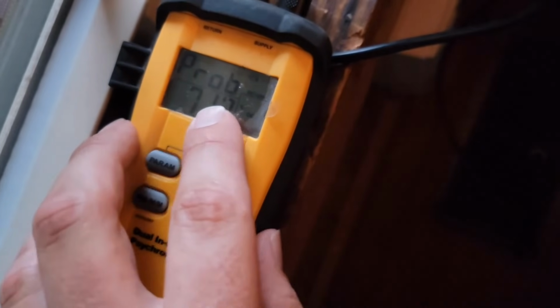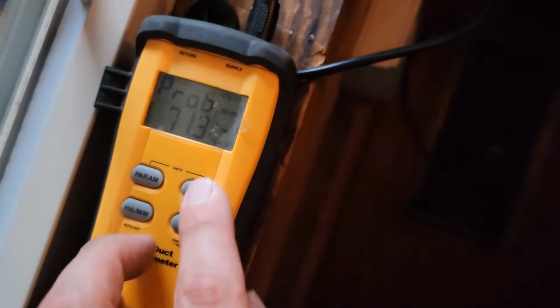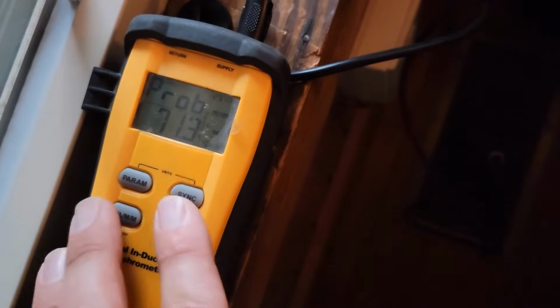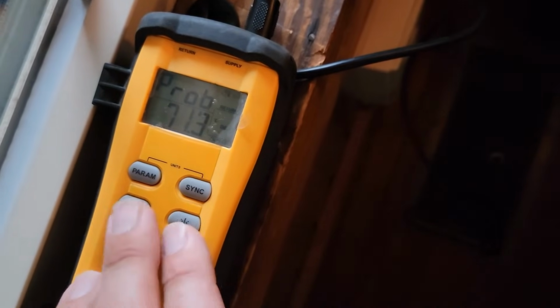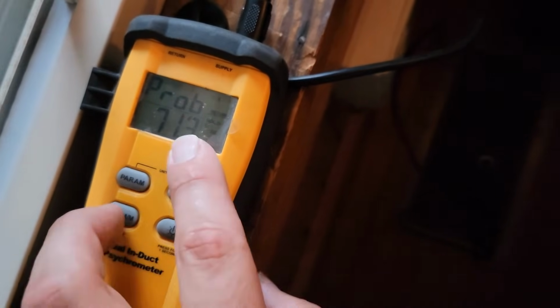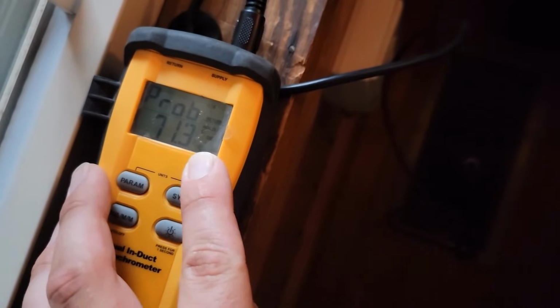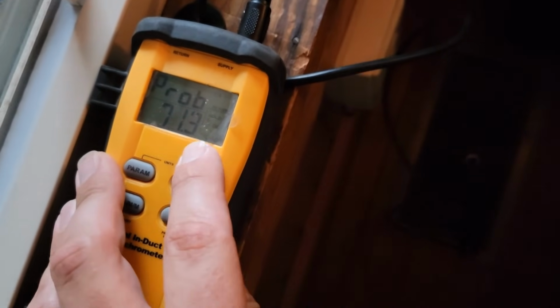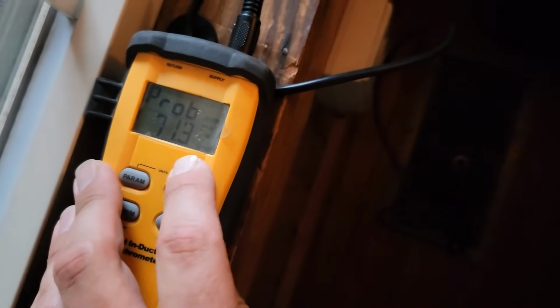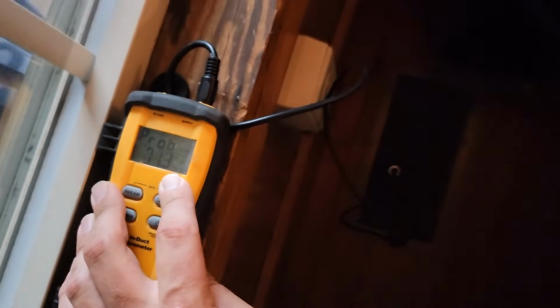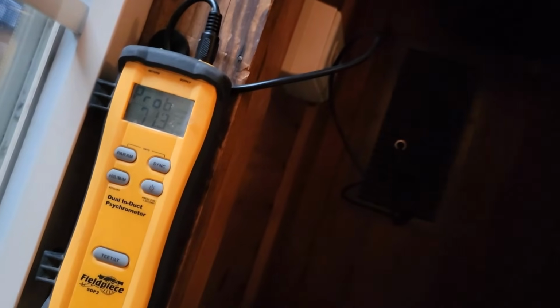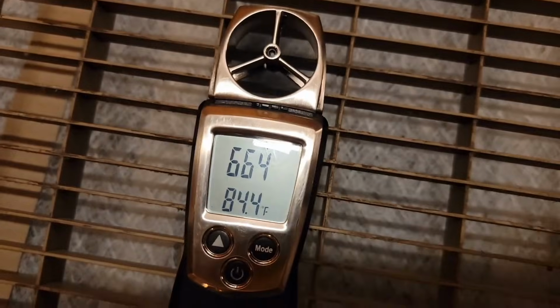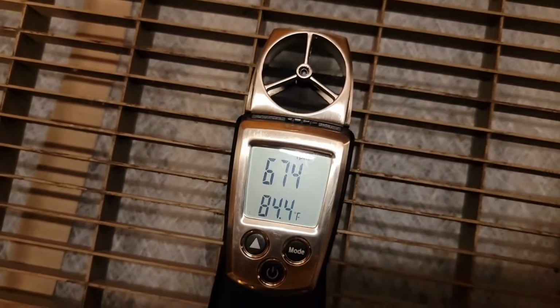So you see the temperature coming out of the supply register, it's only 71 degrees. For it to be a 20-degree split, it would have to be at least 66 because it's 86 in here right now. Since our return is at like 600-700 feet per minute and it doesn't need to be more than 500, I'm going to slow the fan speed down so that I can get a better temperature split. All right, so this is what our feet per minute on that return grill is.